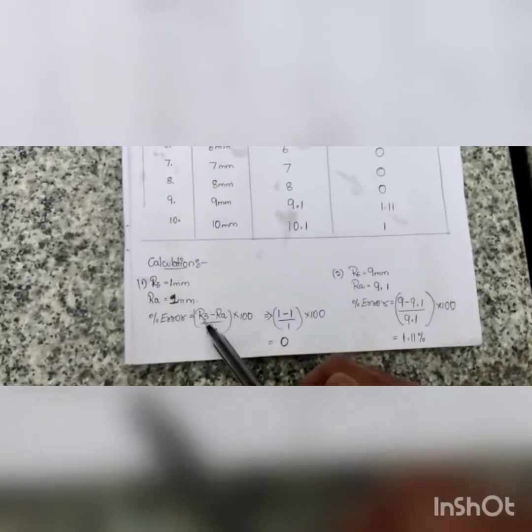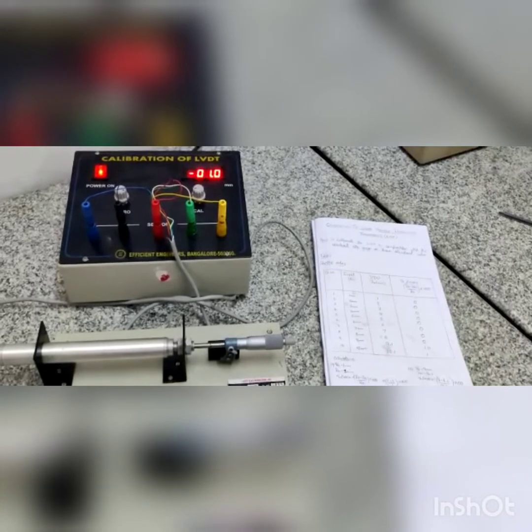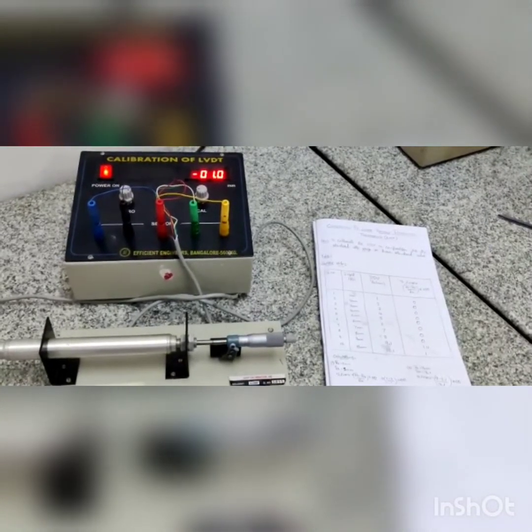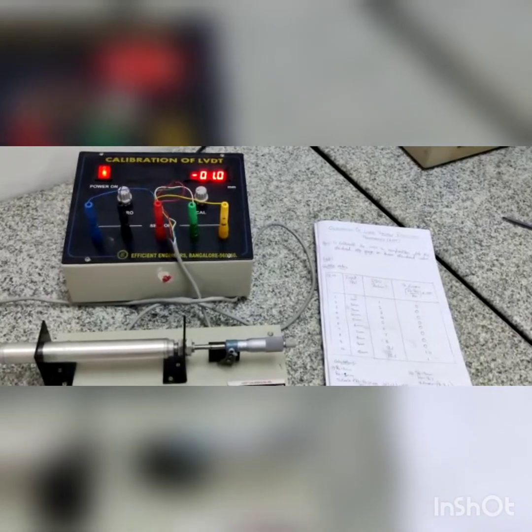These are the negative side readings — the left side of the null point. The percentage error is calculated by the formula RS minus RA divided by RA into 100. The first reading gives a percentage error of 0. From the readings that have been tabulated, we can determine the percentage error of the LVDT machine. These are our results.